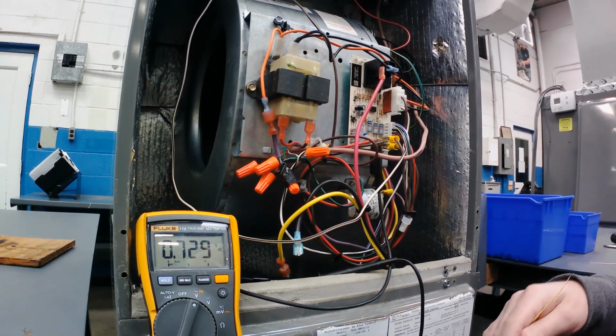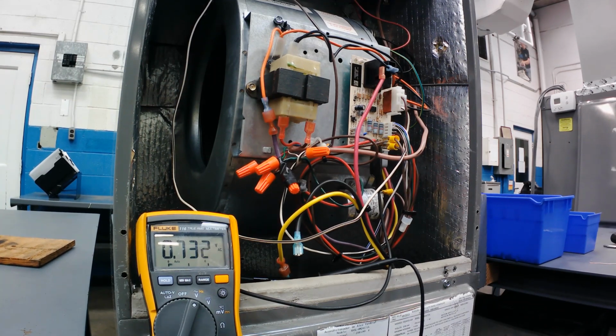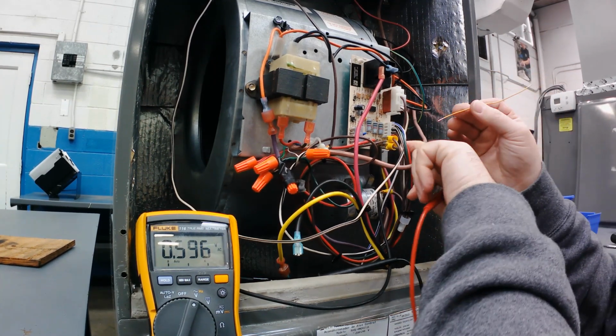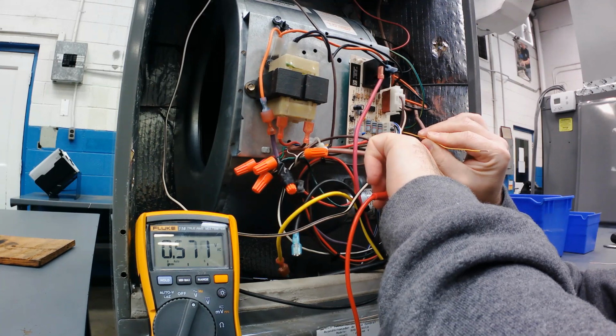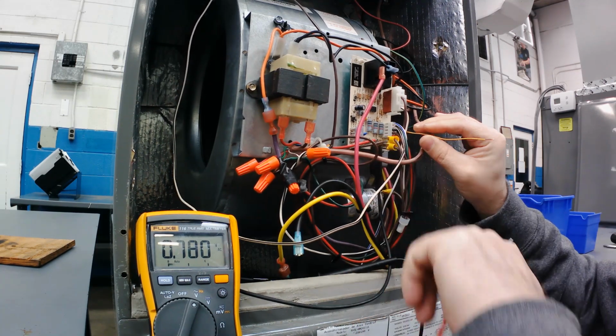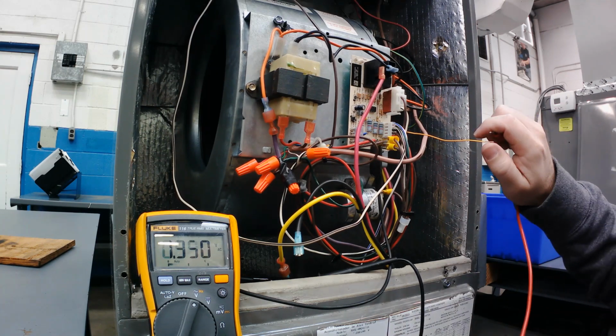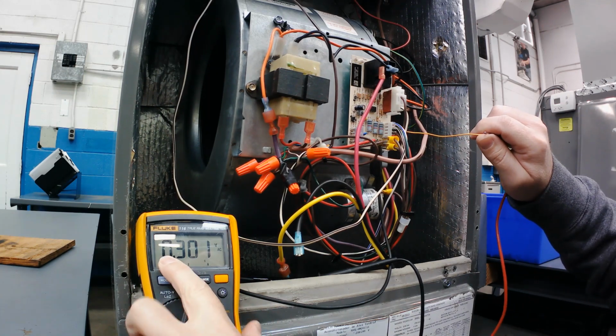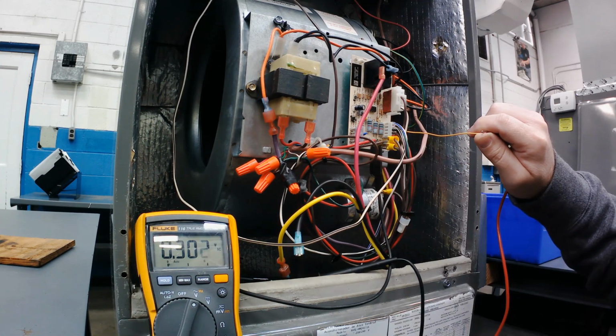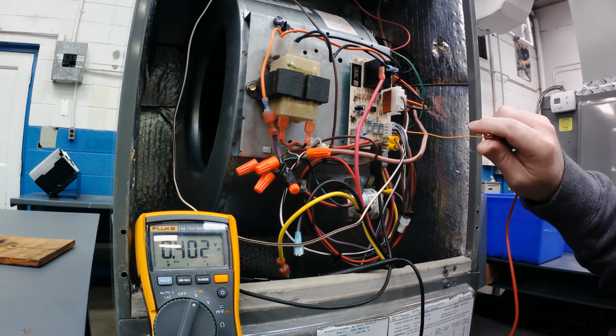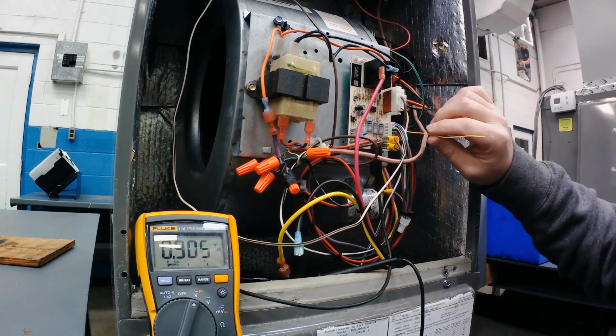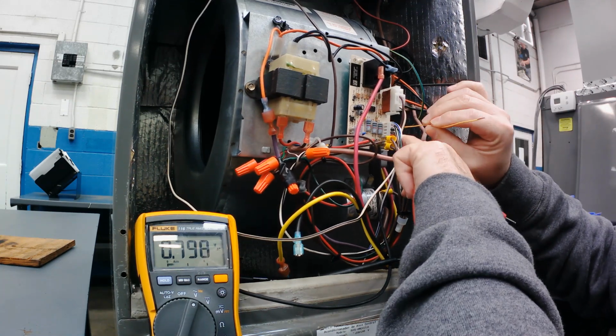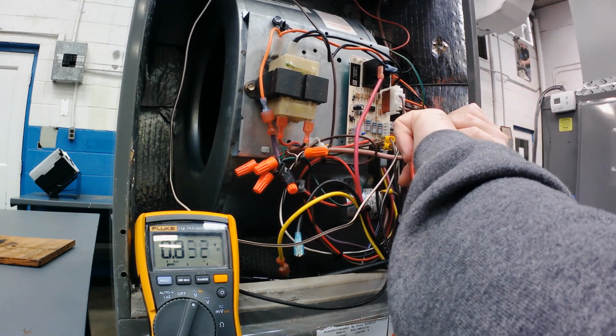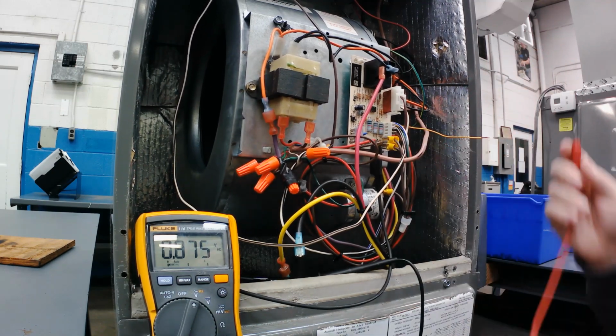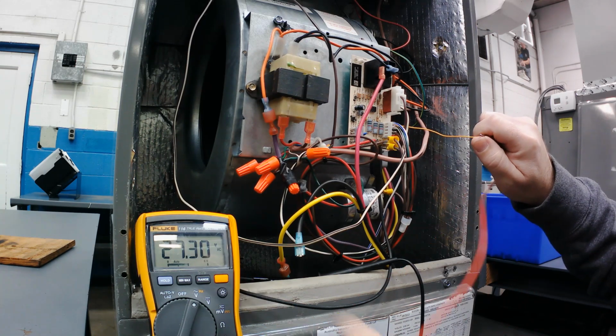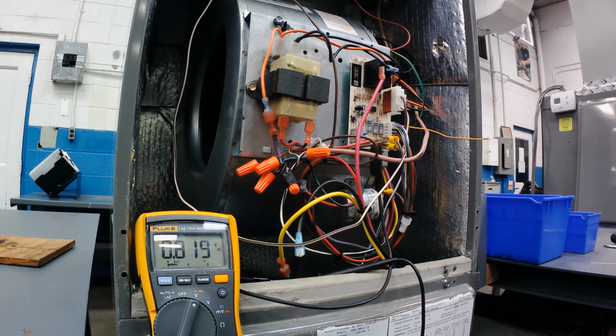Now, on this one, the fan coming on does not necessarily mean that G got energized. So what I would do is move that wire on the plug, and I'm going to put my little thermostat wire on G. Now, if the thermostat is sending 24 volts, which it's not, it's 0, why is my fan on? This goes back to the whole purpose as to why the heat, the W circuit, is on this board. So I'm going to move this wire off of the G and plug it in on the W circuit. And if we have 24 volts on this, which I do, so my heater should be on.